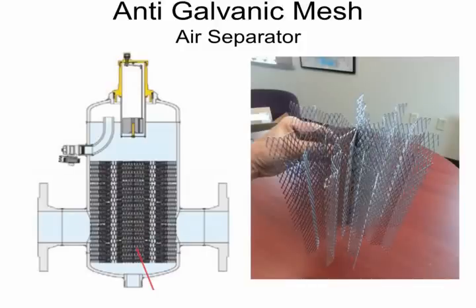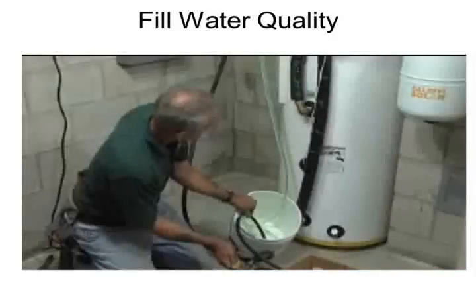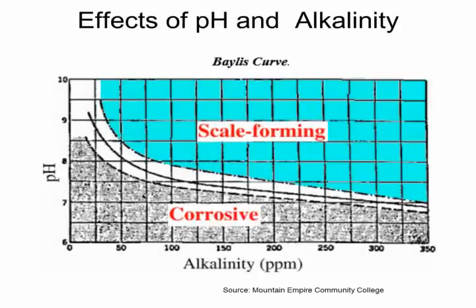And one of the things that we do with our commercial meshes, we use stainless. And if you remember from the galvanic chart I showed you a few slides back, very, very noble, and it won't succumb to any type of galvanic attack. Other makes have been out there that use plated metal of some sort, less noble and potentially less withstanding of galvanic attack. So both galvanic attack and limescale is largely a function of the quality of the water that you put into your system. In fact, almost entirely.